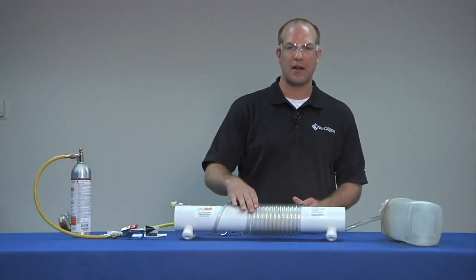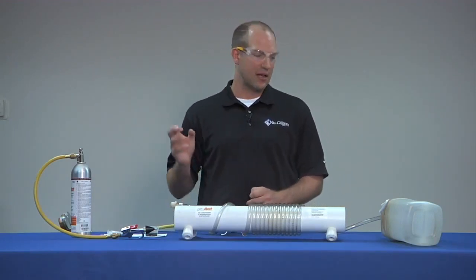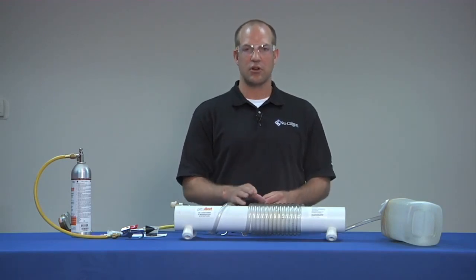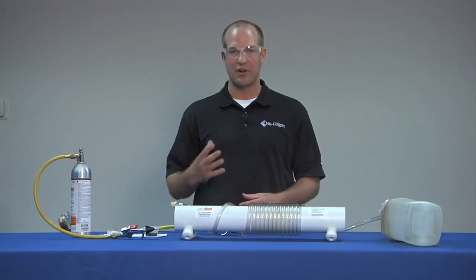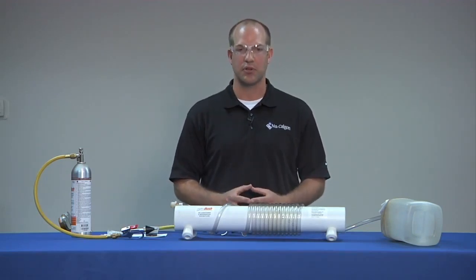Now you can see the lines are adequately cleaned. All of the burnt oil and any other residue that may have been in the line has been adequately cleaned and out of the system. RX11 Flush also has an optimal boiling point at 106 degrees Fahrenheit, which allows it to be completely removed after vacuum is pulled on the system.